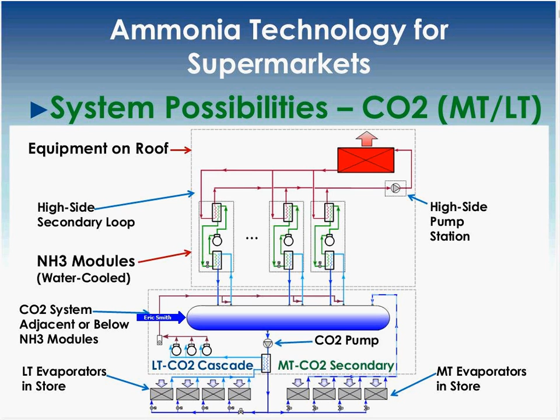This is an example of a supermarket that employs an ammonia and carbon dioxide system in Australia. In 2008, that's 2 modules. Low temp is 112,000 BTUH. Medium temp is 850,000 BTUH. There are 2 flooded modules on the roof for the primary system, and the carbon dioxide system is in a mezzanine below. These are considered fairly large modules. One idea floated around is that the charge be limited to 100 pounds, so there would never be a possibility of having to report a leak to CERCLA or EPCRA.